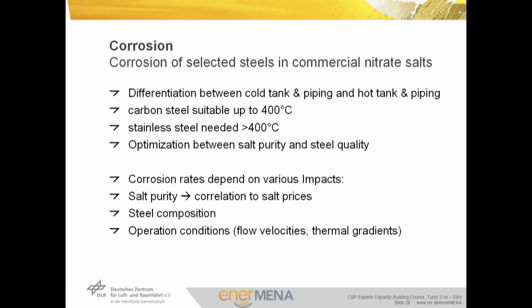Corrosion plays an important role in the design of two-tank molten salt storage systems, and detailed knowledge is critical for cost-effective design. Since corrosion is strongly dependent on temperature, the design of the cold tank is usually different from the hot tank. Carbon steel is suitable up to 400°C, while stainless steel is needed above 400°C. The purity of the salt also affects the corrosion rate, and a cost optimization should be done for salt quality and steel composition.